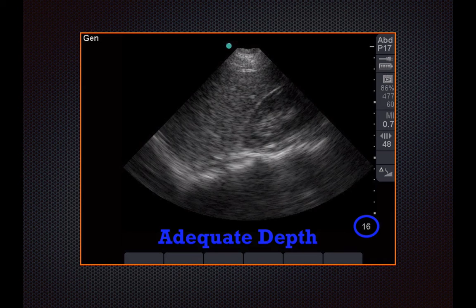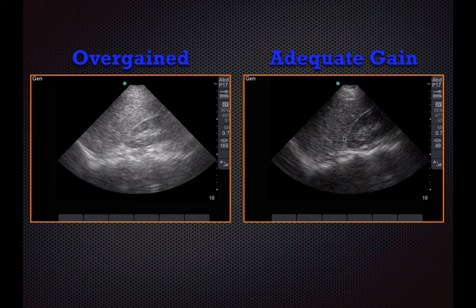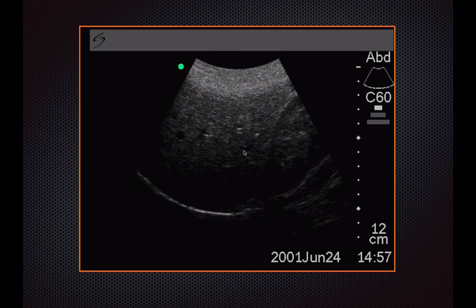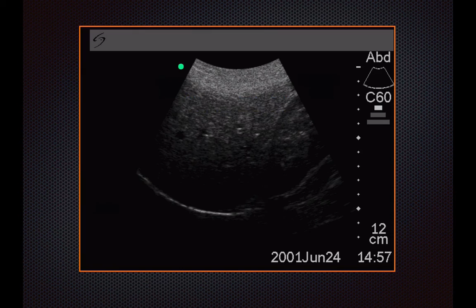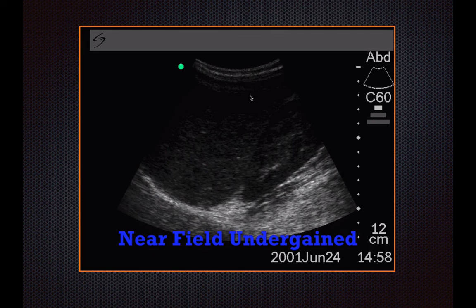And for all of us who remember black and white TV, all those 50 shades of gray scale, you have the gain. The gain is on the left side of the screen if you're using the M Turbo, and you have near field and far field. Basically the gain is the way the machine interprets the echoes. You can be over gained, on this side, maybe a little too bright, versus adequate gain, when you see proper images. Gain changes the overall strength of the returning echoes, so it helps you amplify if you need to. This looks maybe okay, the near field versus the far field. Probably a little under gain in the far field, versus the near field here, which is under gain. This is maybe a little bit better.